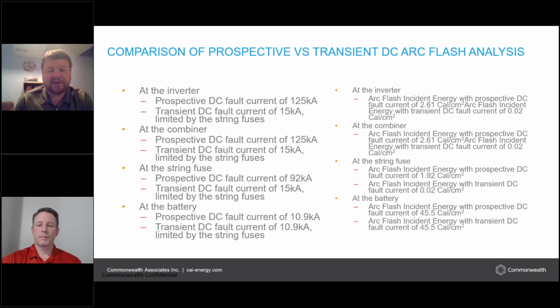And we can see that our arc flash levels here for this particular example are incredibly high. Anything that's over 30 cals is something of concern. Over 40 cals, most of the time we would not recommend working on energized. And then back to Chris's point, you can never really de-energize lithium-ion battery energy storage systems. So even at 0% charge, those batteries still contain about 80% of their total energy. So this is a major issue on how workers are going to be able to work on equipment.